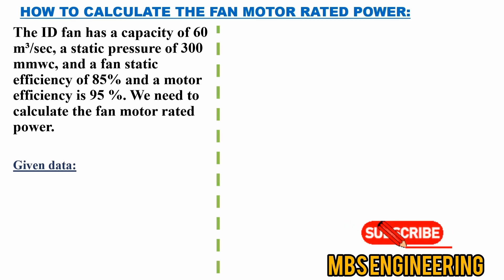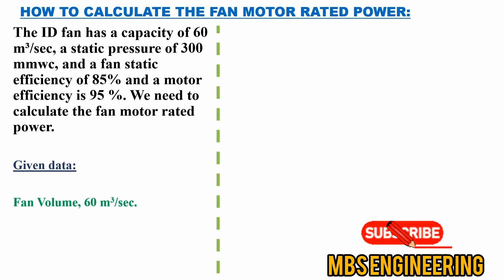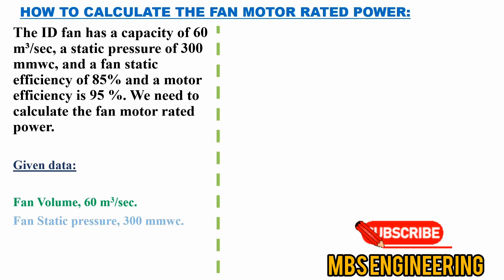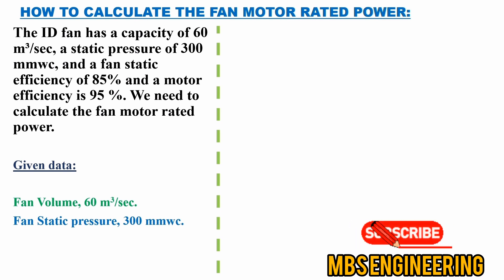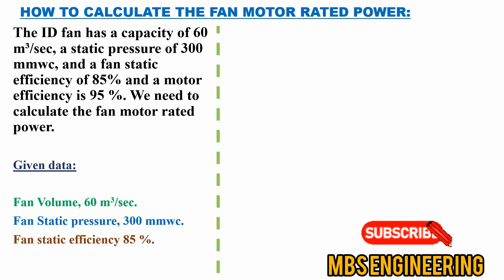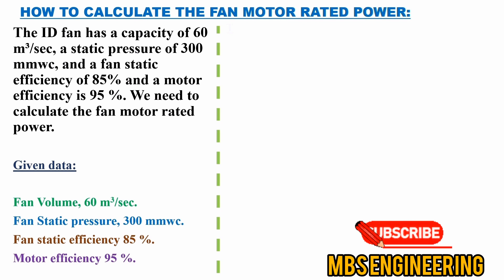Given data: the first parameter is the fan volume, which is 60 meter cubes per second. The second parameter is the fan static pressure, which is 300 millimeters of the water column. The third parameter is the fan static efficiency, which is 85%. The fourth parameter is the motor efficiency, which is 95%.